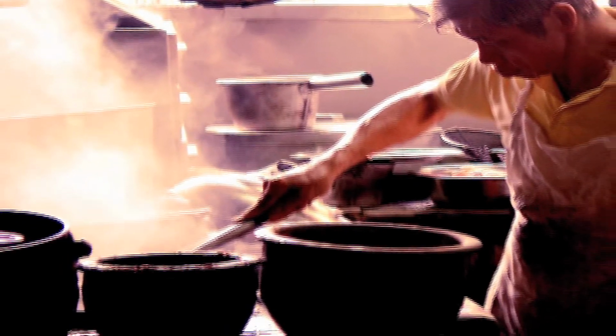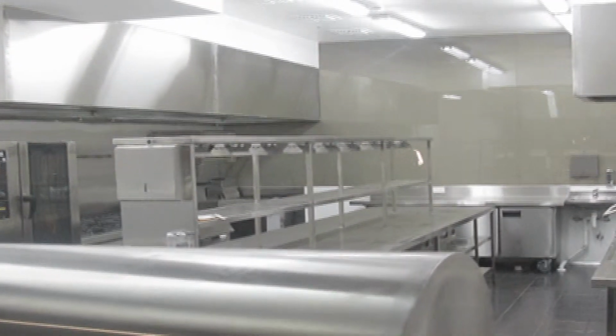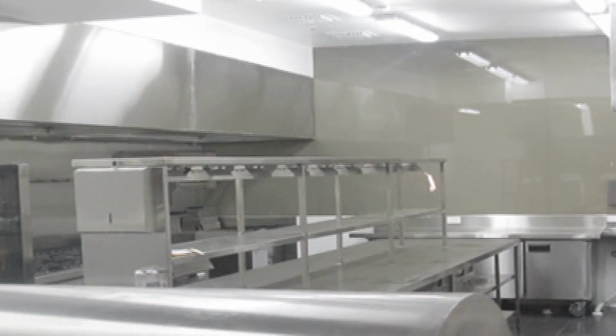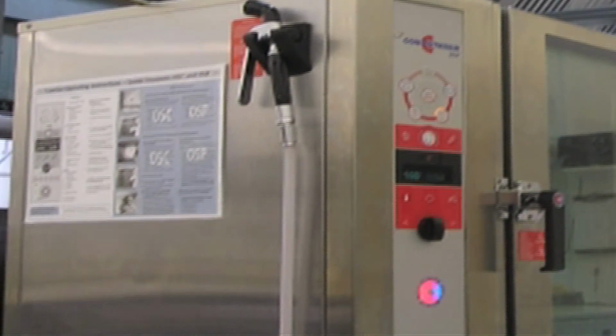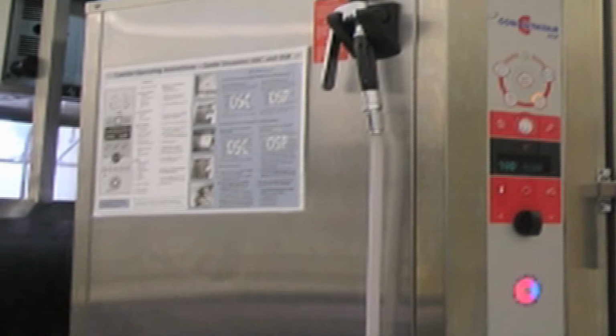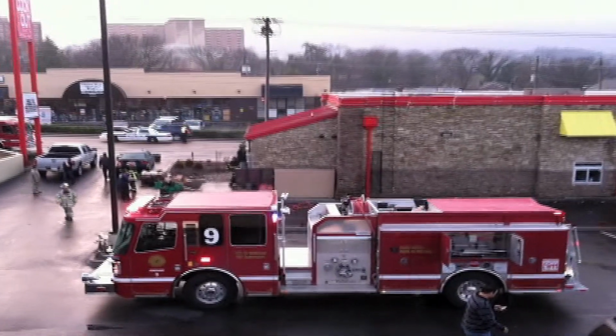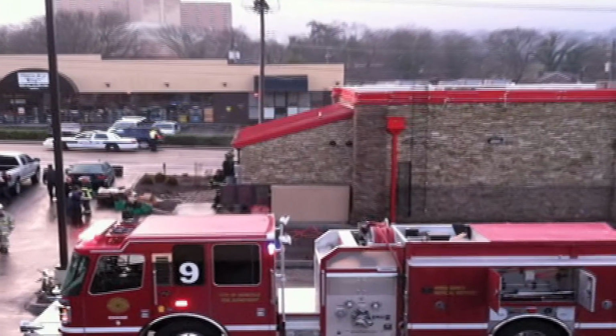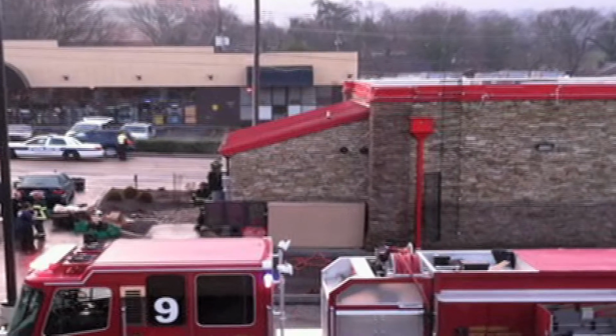Oftentimes, a kitchen fire can be traced back to the original design. The design could be flawed. We could have the wrong gauge of metal. We could have unwelded duct. We could have the wrong installation. There are many factors, no clean outs, many other factors of design that would cause a fire to spread beyond the scope of what it was designed for.